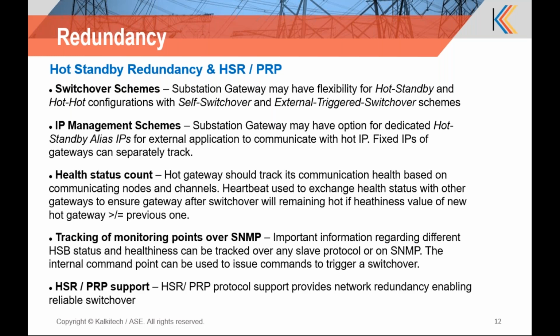For network redundancy, the PRP HSR protocol is supported, and it ensures bumpless data even though a single network fails. It ensures that the data always gets routed through the alternate route also, and both copies of the data will be available if both networks are working. If any network fails, the data through the other network will still be available.